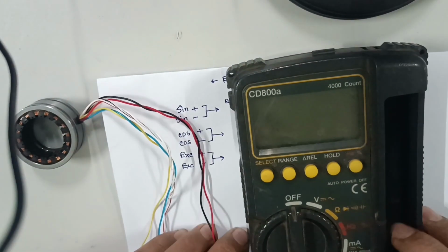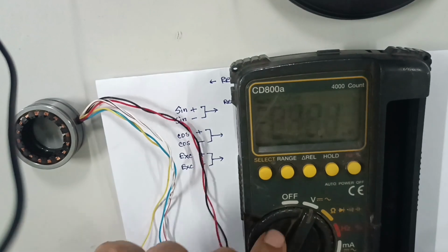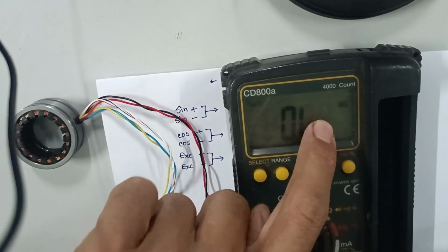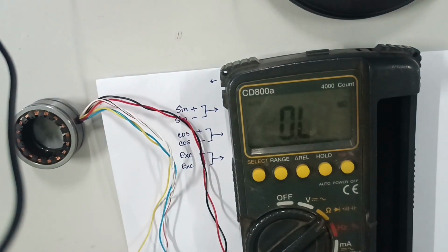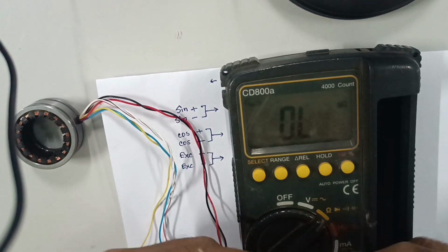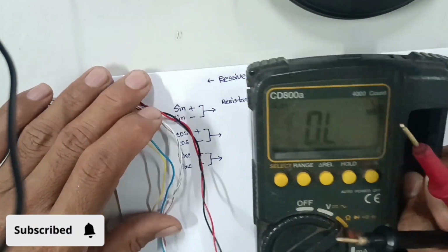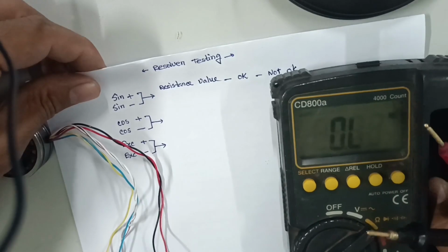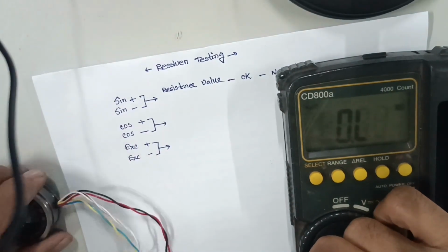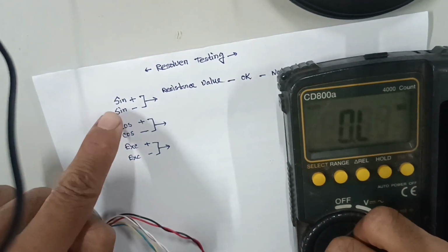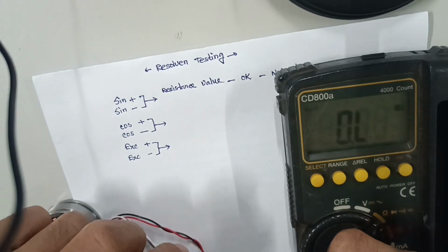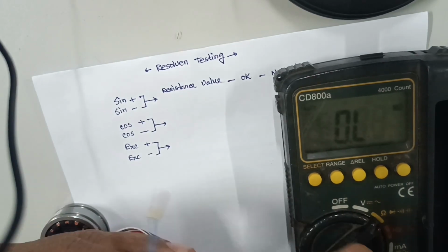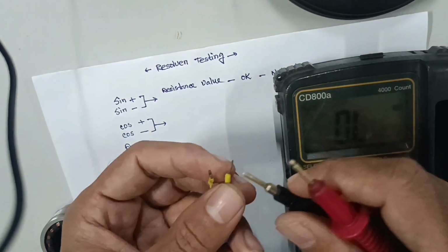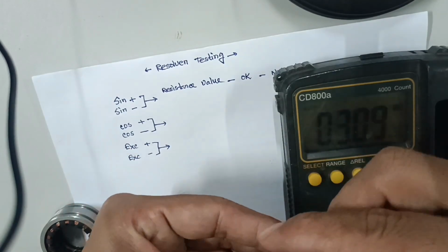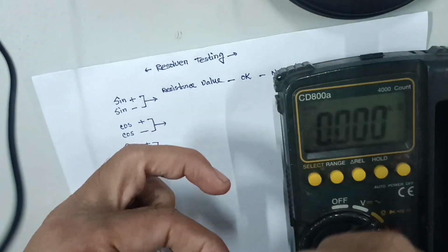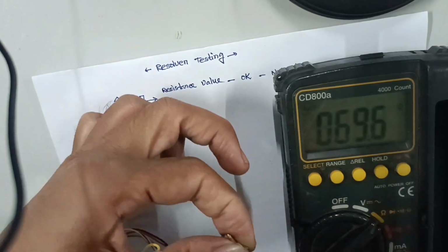That is the connection. You can see I'm measuring now with the multimeter for excitation. First I want to check yellow and blue, sine plus and sine minus. I think the result should be similar - the output cables, both sine and cosine, the resistance will be similar. Otherwise if the values aren't similar, you can understand that the resolver is faulty.